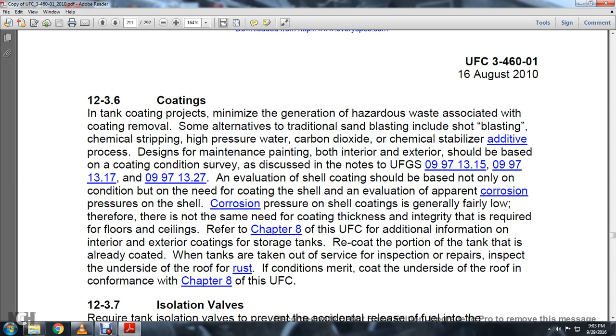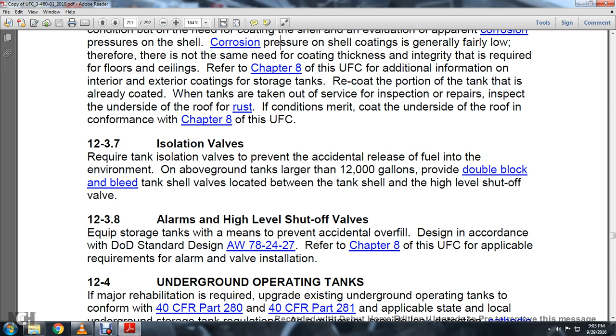12-3.7 isolation valves. Require the tank isolation valve to prevent the accidental release of the fuel in environmental above-ground tank storage of 12,000 gallons, provided with a double block and bleed tank valves located between the tank shell and the high-level shutoff valves. 12.3.8 alarms and high-level shut-off valves. Equip the storage tanks with means to prevent accidental overfill, designed according to the Department of Defense standards AW78 2427 for the Chapter 8 of the UFC, the applicable requirements of the alarms valve installations.